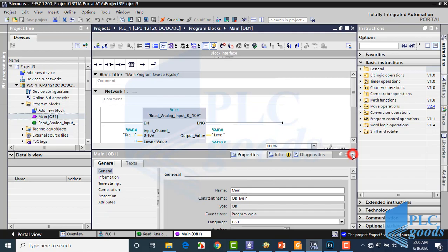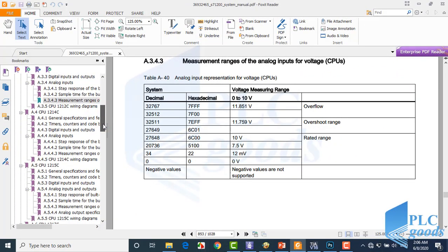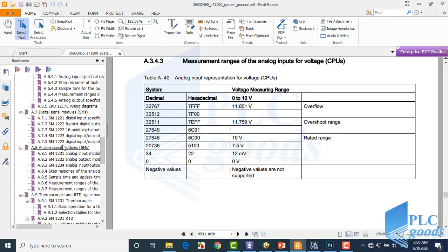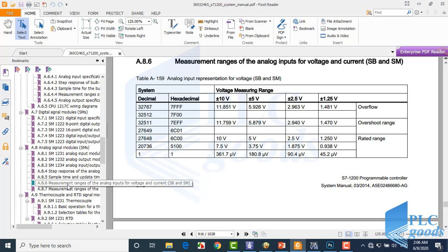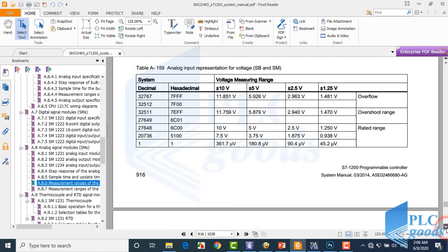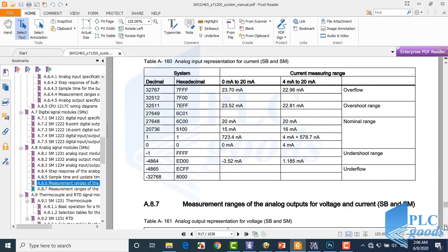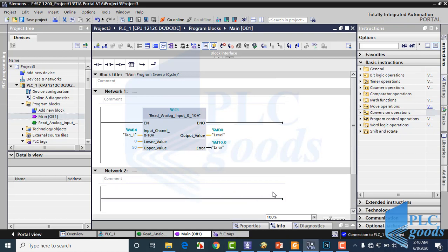Before starting programming, let's find the measuring range table of the inserted module. As you see, to have 4 mA and 20 mA, I need to send 0 and 27648 to the output address. To have 16 mA, I need to send this corresponding number. So let's start programming.